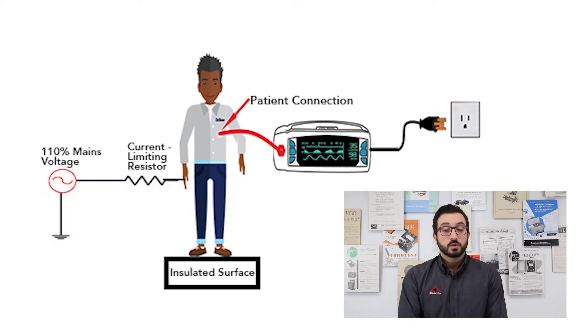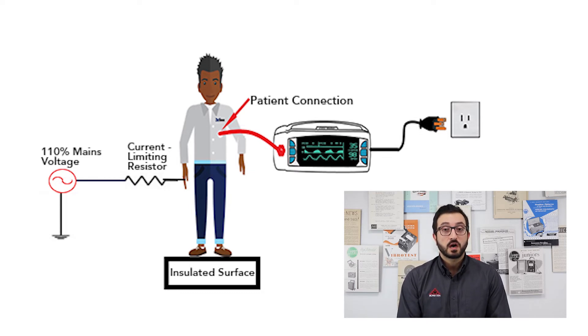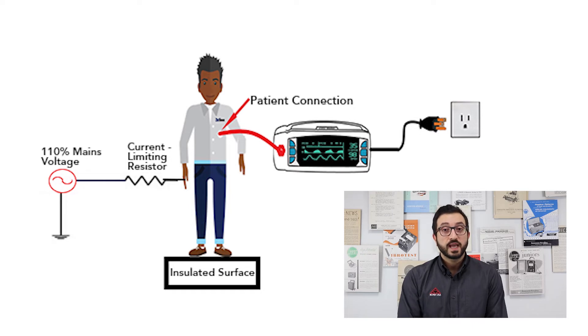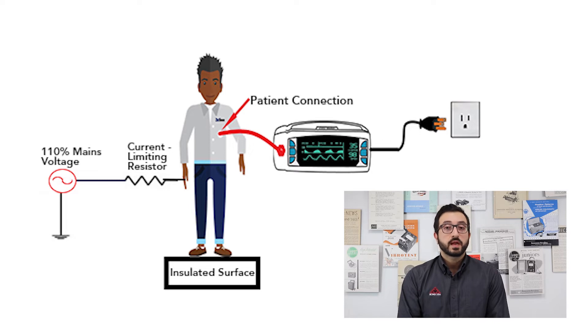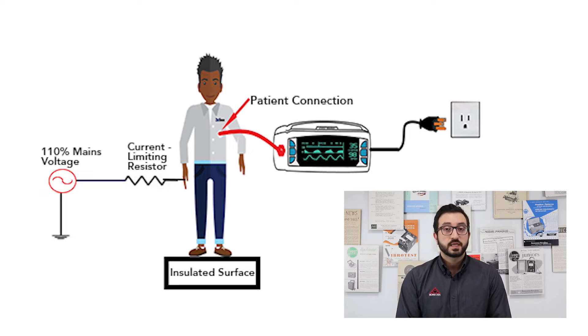In other words, applied parts that may come in direct conductive contact with the patient's heart or other applications as considered necessary. During the test, leakage current of each applied part is measured while applying 110% of mains rated voltage through a current limiting resistor.